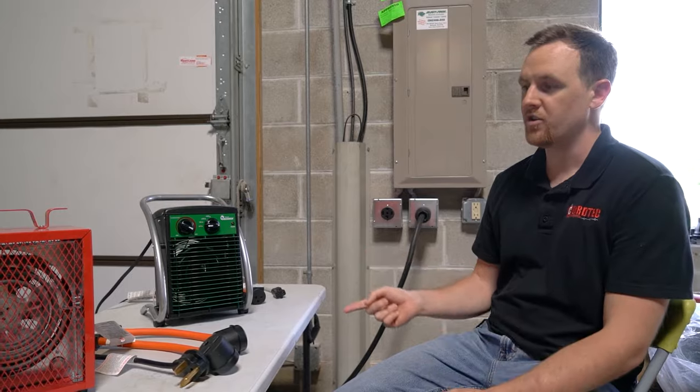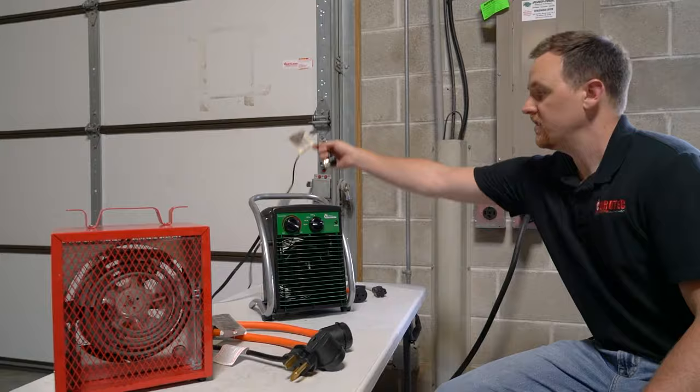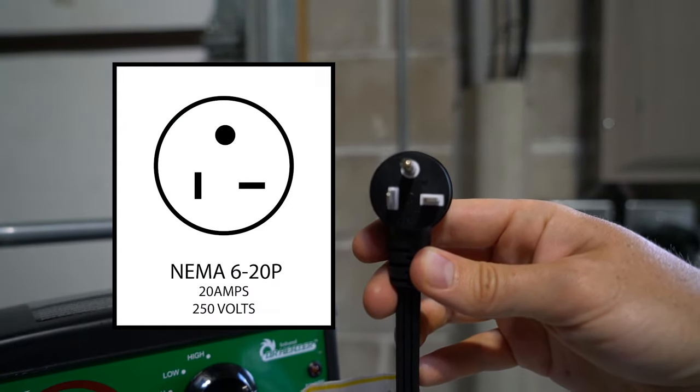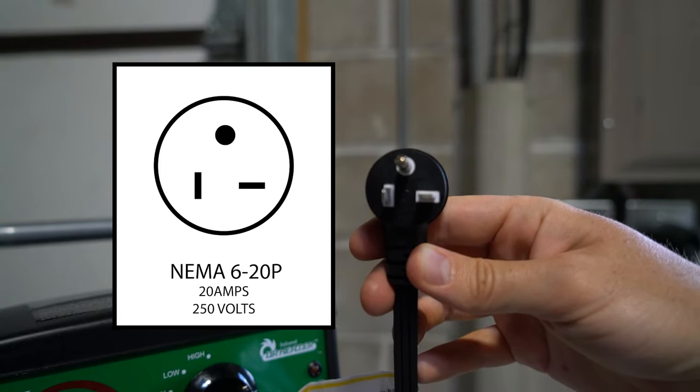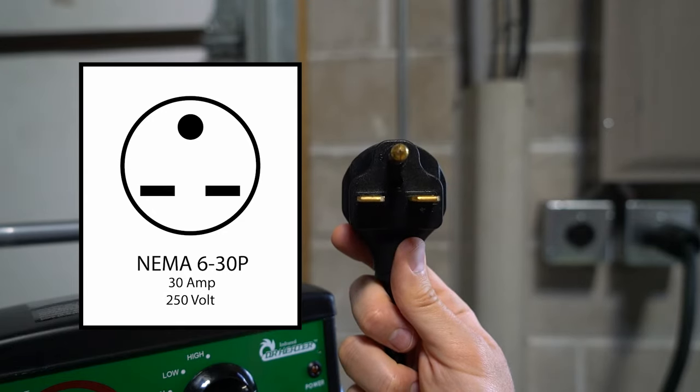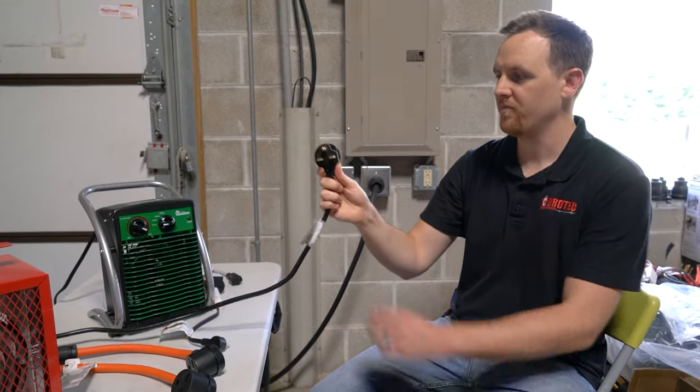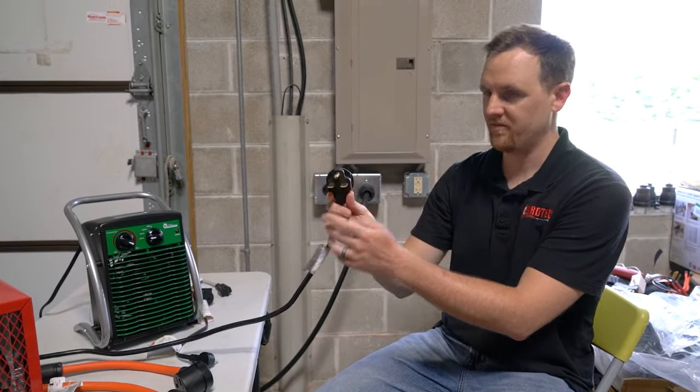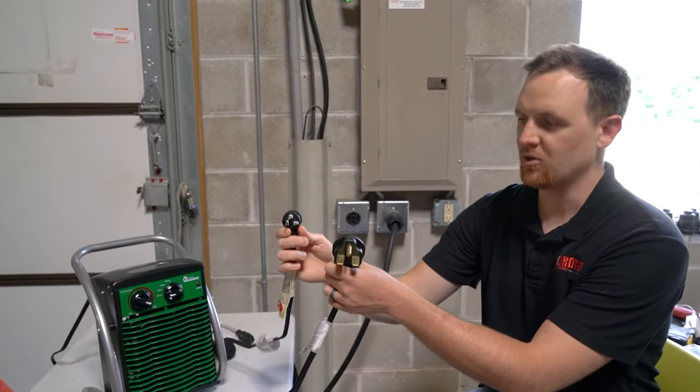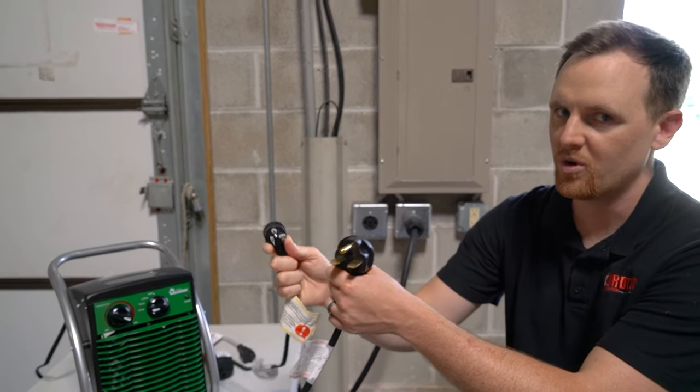Here we have two portable heaters that are strictly wired for only 220 volt usage. Over here, NEMA 6-20 and NEMA 6-30 and these are both wired specifically for 220 volt usage. So two hots and a ground and it's the exact same way for the 6-20, two hots and a ground. So it's only going to be able to be used at 220 volts and it needs a 220 volt outlet.